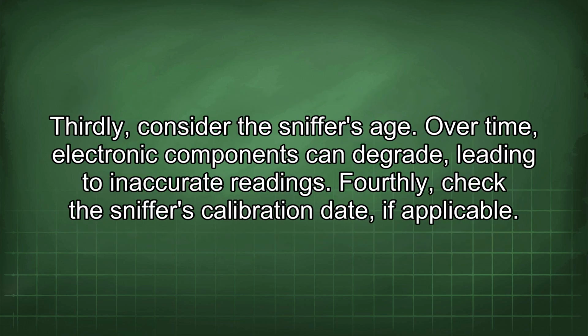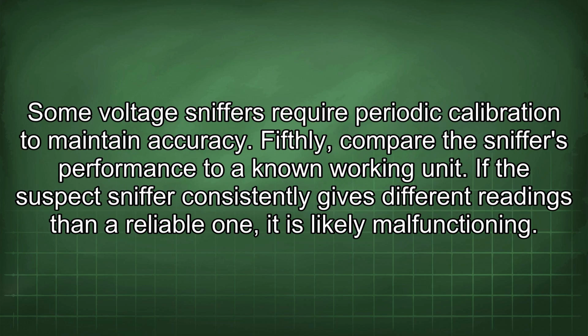Over time, electronic components can degrade, leading to inaccurate readings. Fourthly, check the sniffer's calibration date, if applicable. Some voltage sniffers require periodic calibration to maintain accuracy. Fifthly, compare the sniffer's performance to a known working unit. If the suspect sniffer consistently gives different readings than a reliable one, it is likely malfunctioning.